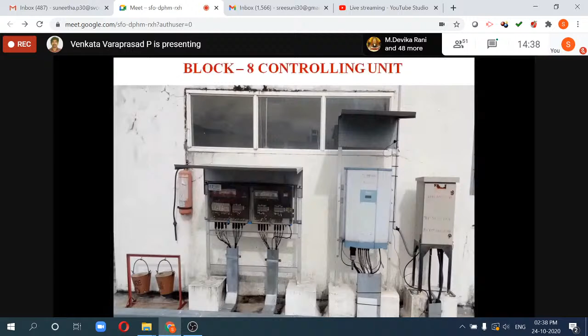The AC 4-core cable is connected to the AC distribution side, presented here with the breaker. From the breaker, output cable is taken outside and connected to the main MCB of each block. Each block has one main MCB, and this cable is connected to that particular point.